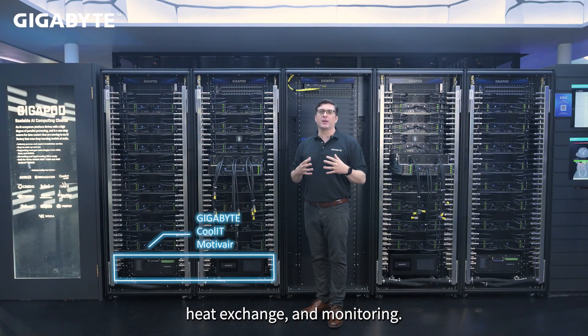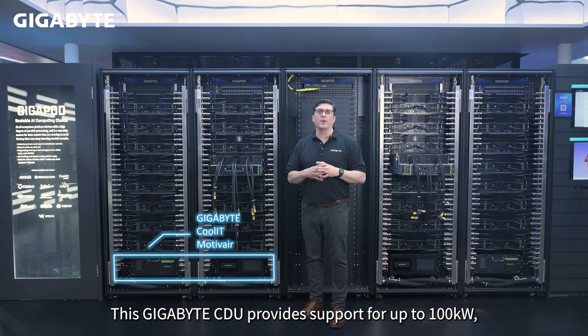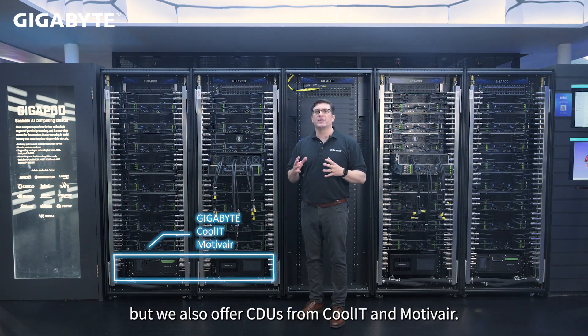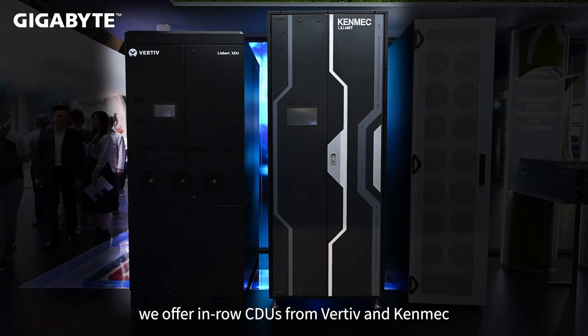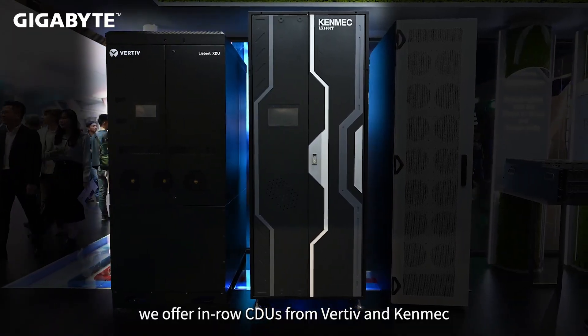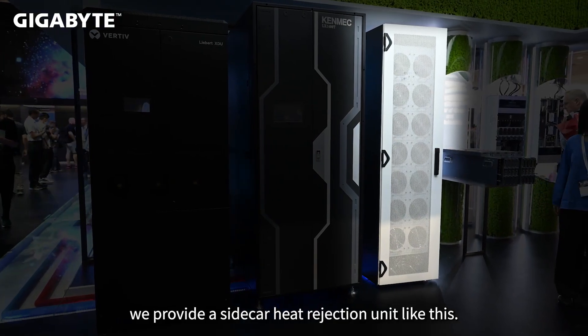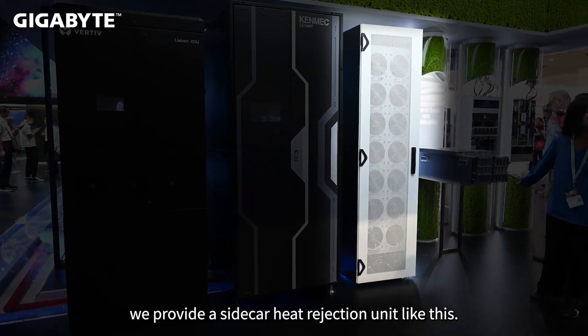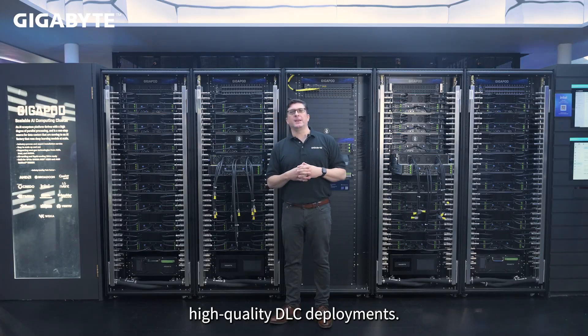Our liquid cooling needs a CDU for pumping, heat exchange, and monitoring. This GigaByte CDU provides support for up to 100 kilowatts, but we also offer CDUs from CoolIT and Motivair. For higher loads or centralized setups, we offer in-row CDUs from Vertiv and Kenmec. Each can cool four racks easily, but they do require a facility water loop. We provide a sidecar heat rejection unit like this. We work with various partners to ensure timely, high-quality DLC deployments.